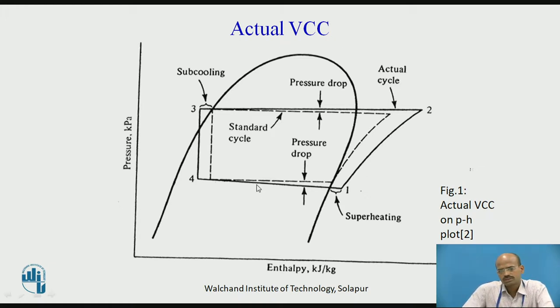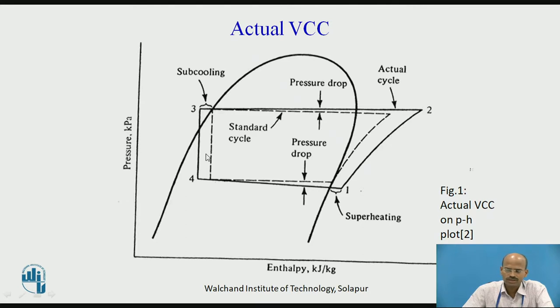In the previous sessions, we have studied the schematic diagram of Vapor Compression Cycle and shown VCC on a p-h diagram. Now, if we consider practical considerations into account, then the dotted line representing the theoretical cycle will get modified into the actual one. In actual VCC, the pressure drop caused due to friction between the refrigerant and the tube wall is considered, along with the wire drawing process, the practical compression process, and the practical condensation process.